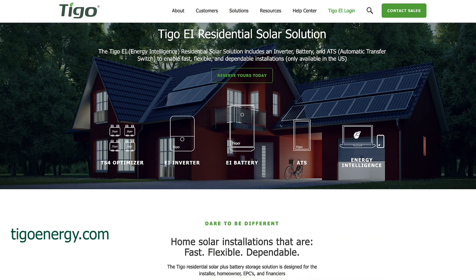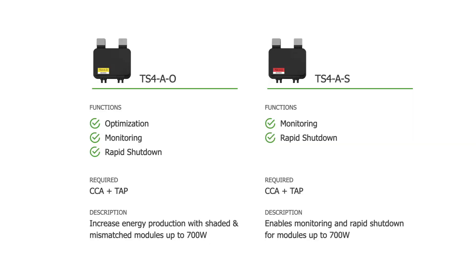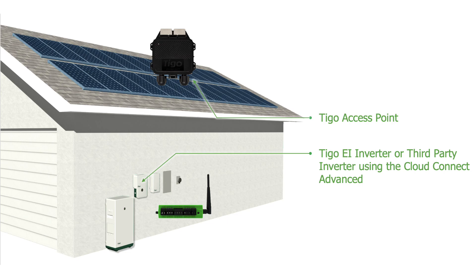When the inspector comes and sees that wire sticking out of the same conduit into the inverter — so if you're using the Tigo EI inverter, which is part of our EI energy storage solution — or you're using our TS-4s for rapid shutdown, optimization, or module-level monitoring, and you're running that communication down from the Tigo access point either to the EI inverter or to the Cloud Connect Advanced, you have to use 600-volt rated wire for residential.